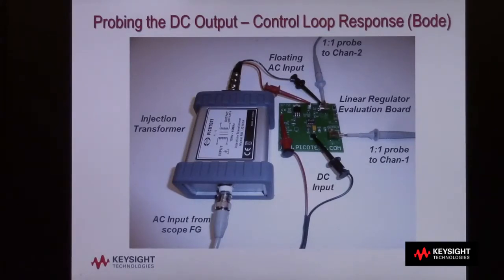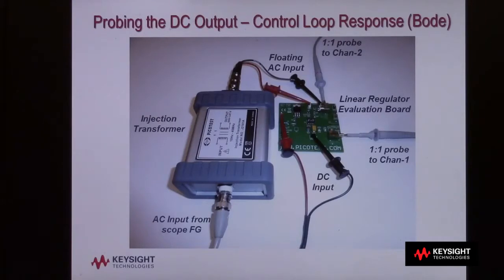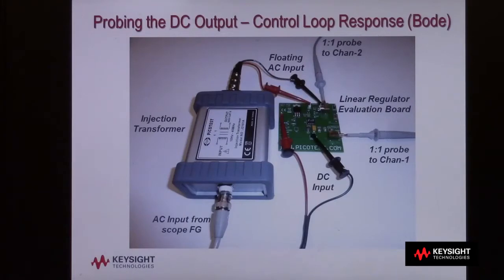At the bottom of this photo, you can see the BNC cable from the scope's waveform generator output connected to the input of the injection transformer. The output of the injection transformer, which is now isolated, is connected across the 5-ohm injection resistor. Proper probing is very critical. We've got to use one-to-one probes to get maximum sensitivity out of our scope to measure very low-level AC signals, and we've got to use very good probing ground techniques so that we don't pick up noise or interference. I'm using solder-in probe sockets rather than standard ground leads, which really act like antennas when you're attempting to measure very low-level signals.